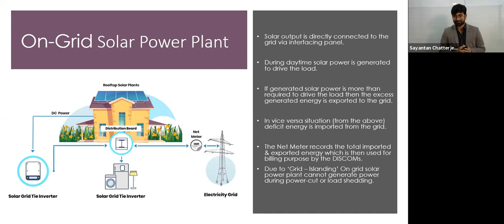Due to grid islanding, an on-grid solar power plant can't generate power during a power cut or load shedding. Why? Suppose in a locality there are 50 houses, and among these, 10 have grid-connected solar power plants. Now if the DISCOM wants a shutdown to repair the line, but the solar plants are still generating and feeding power into the grid, there will be no real shutdown. There will be a huge accident, and it's not possible to inform every household to take a shutdown. So there is a mandate: every grid-connected solar inverter should have grid islanding facility. Otherwise, it won't be permitted.